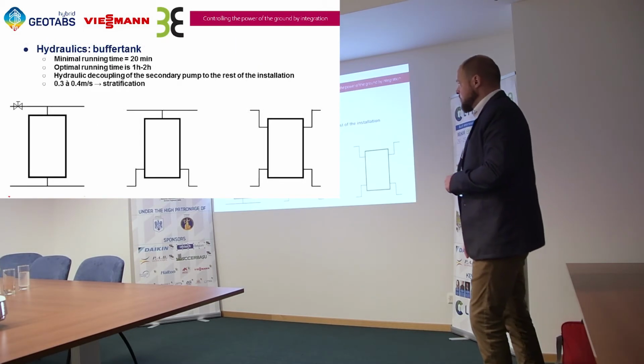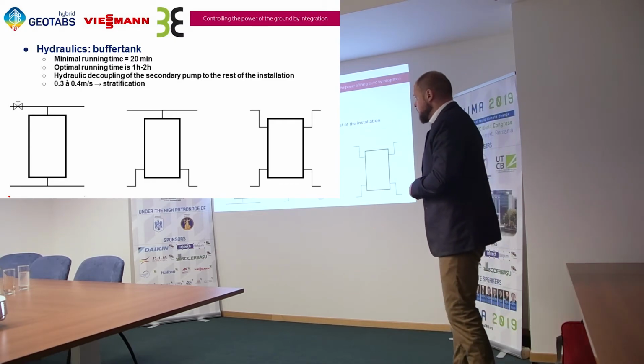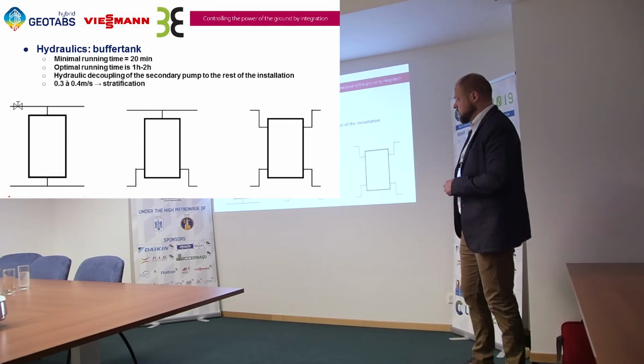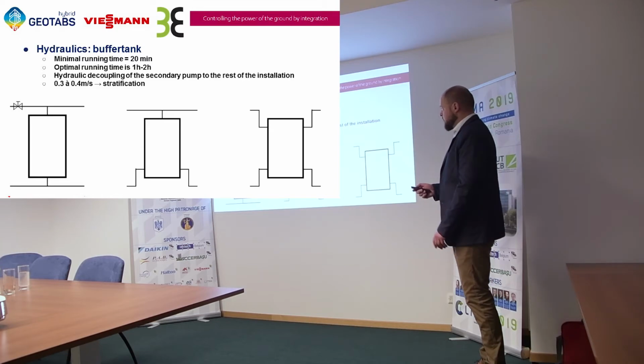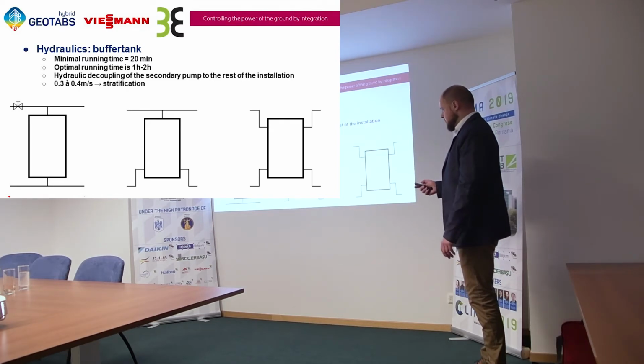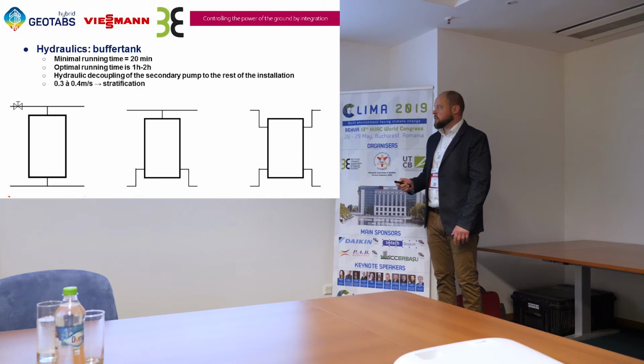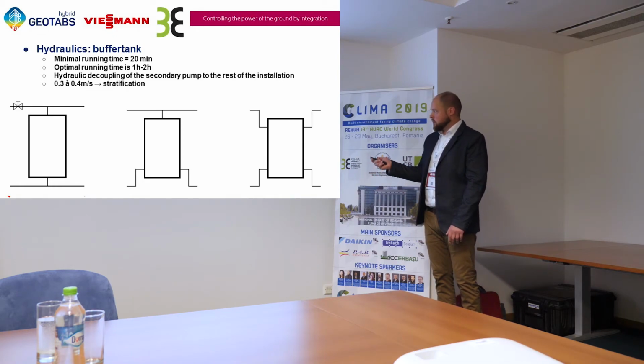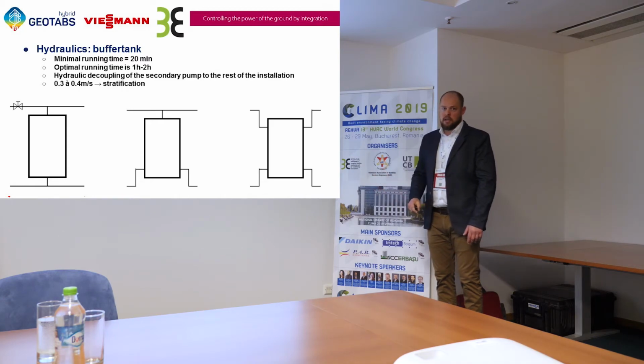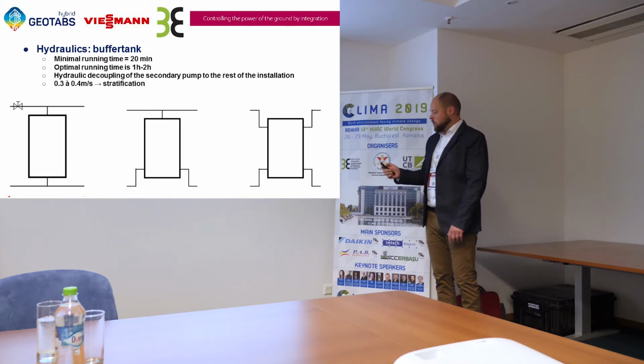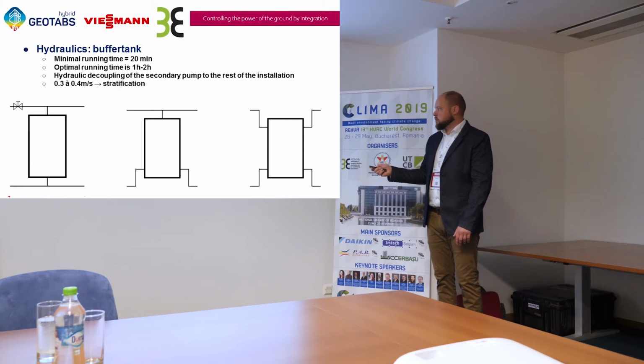Then a bit about hydraulics, how to connect a buffer tank. There are many visions. We have done a lot of tests in the field, and we see that some systems work better than others. This is the usual way we use it in domestic applications, small buffer tanks. So the input from the temperature is on top, and the departing temperature to the installation is here. Return from the installation, return to the heat pump.